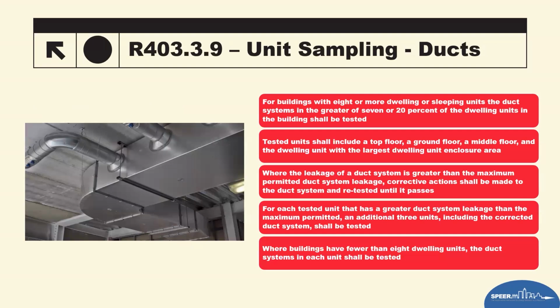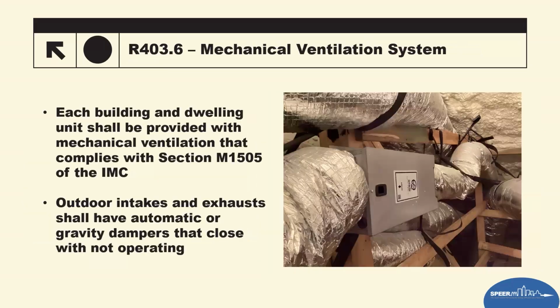That also applies in duct testing for multifamily, which is the sampling protocol. Same thing exists. We're looking at 8 or more units, and you must test at least the greater of 7 or 20%. You must have a sampling protocol that has tested units that include top floor, ground floor, middle floor, and then the largest dwelling. Same thing happens: if you have one that fails, it's got to get corrected and fixed. Anytime you have a failure, you add 3 more. And then, of course, anything less than 8 units, you have to test every single unit. So that makes it easier for multifamily to address that part of it. That came from the commercial side of apartments, and now it's been brought into the residential side of apartments as well.